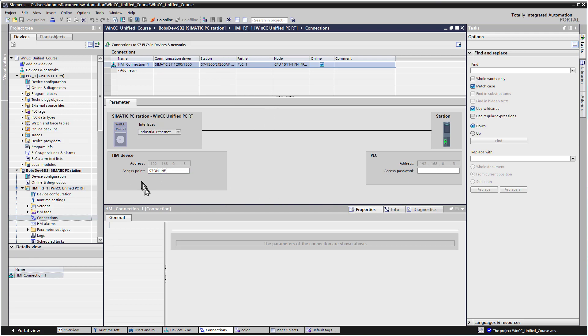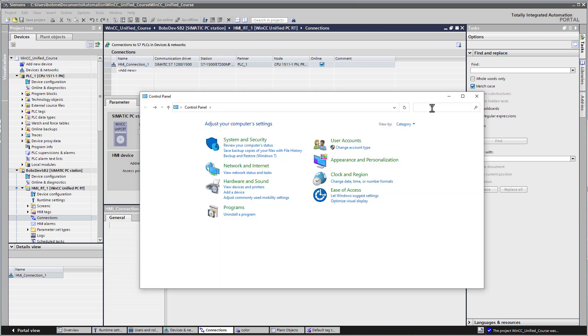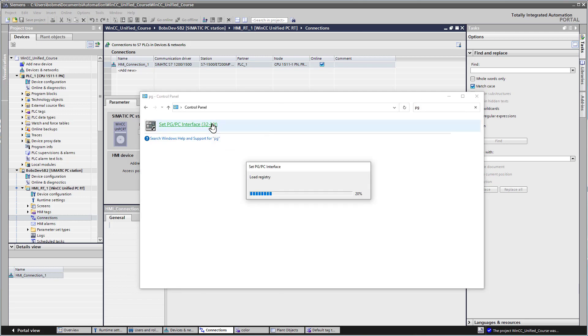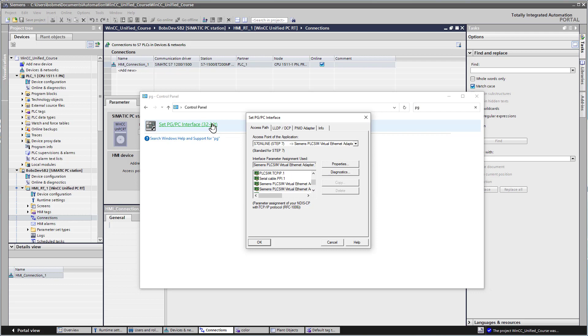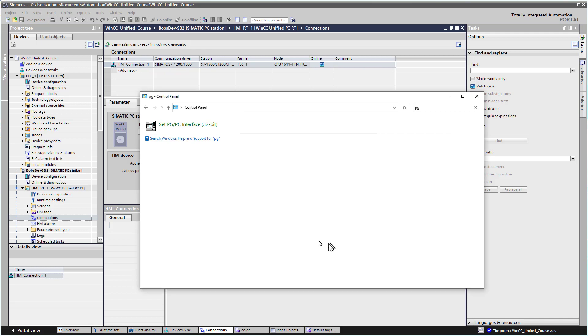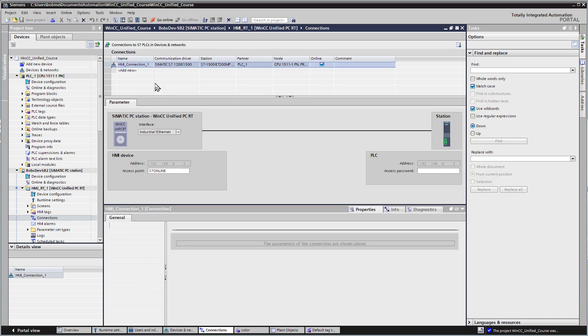Notice that we're using the S7 Online access point. We have to go to our PGPC interface and make sure that S7 Online is hooked up to something that we can have a virtual network with. I'll pull up Control Panel, and you can search for PG. Notice that I have S7 Online set up to the Siemens PLC SIM Virtual Ethernet adapter. You need to do this because we're going to be simulating and that's going to be networked.